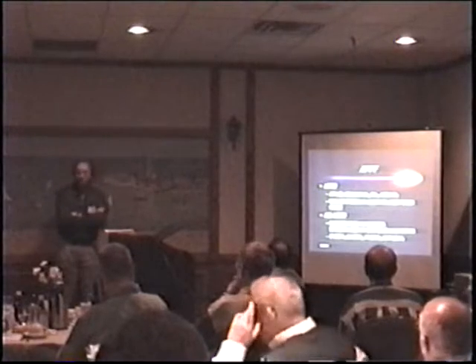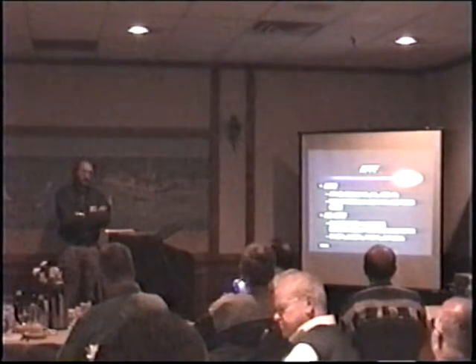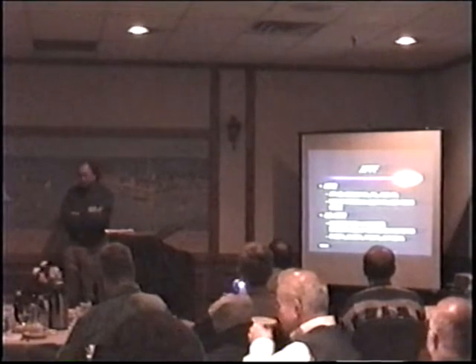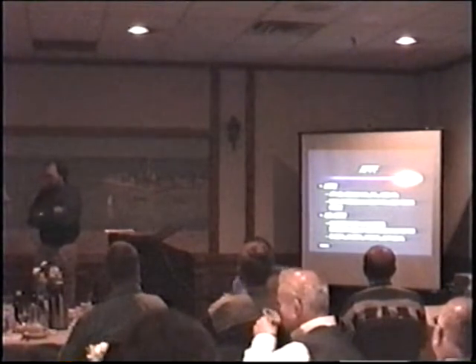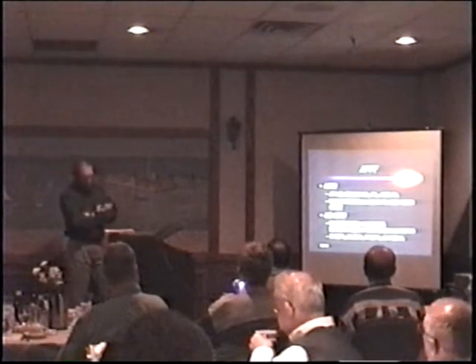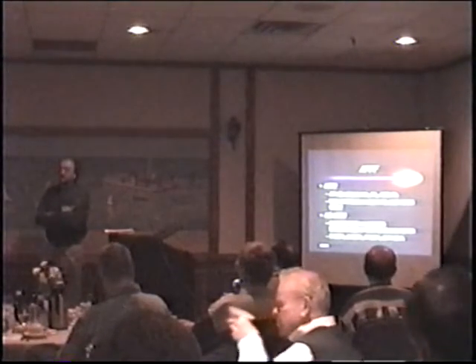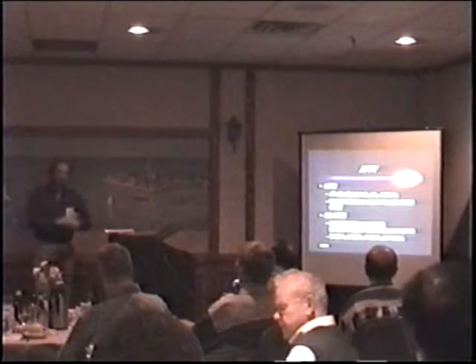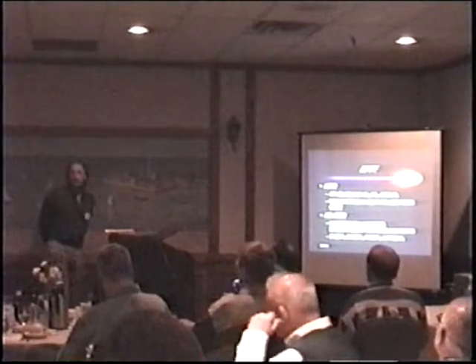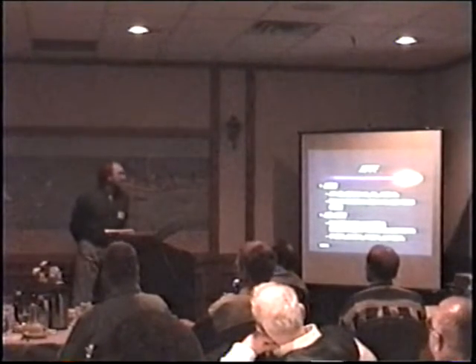AFFF is strictly for use on hydrocarbon-based fires: fuel oils, jet fuel, that type of flammable liquid. When you get into flammable liquid storage and chemical areas, now you're looking at water-soluble materials, and you've got to go with the alcohol-resistant AFFF. Basically that's an AFFF that's had polymer added to it, where AFFF is more like apple juice, alcohol-resistant is more like snot. Different manufacturers, different consistencies.